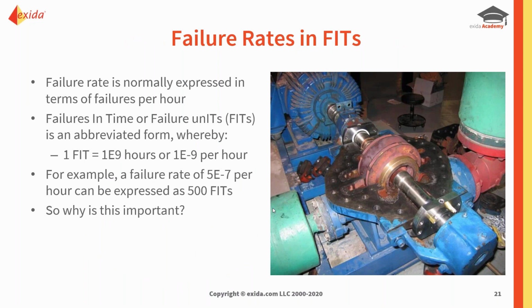So let's talk about FITs, failure rates and FITs. I mentioned that failure rates are normally expressed in terms of failures per hour, but the FIT is an abbreviation that we can use just to help simplify things. There are two definitions that we've seen for FITs. One is failures in time, the other one is failure units. So it's an abbreviated form whereby a FIT is basically a billion hours, or 10 to the 9 hours. And of course, it's 10 to the minus 9 per hour.